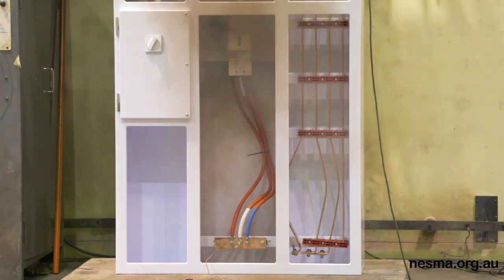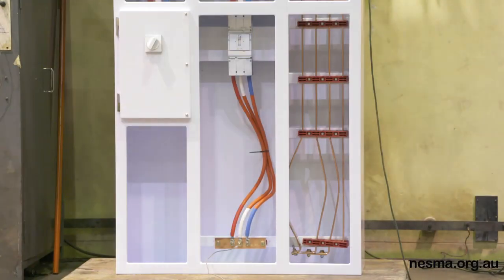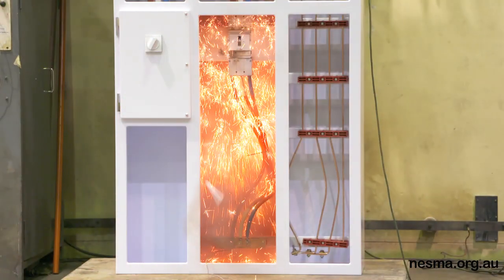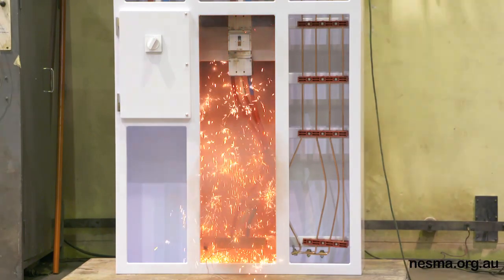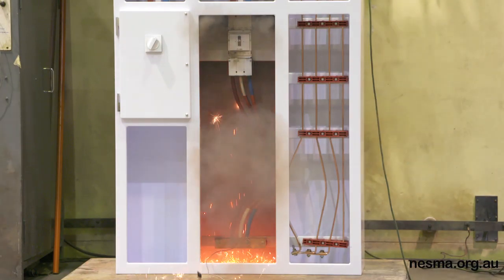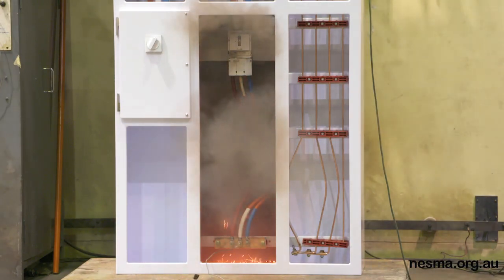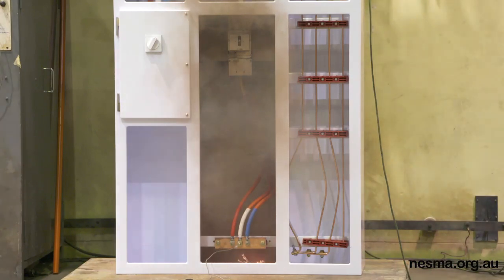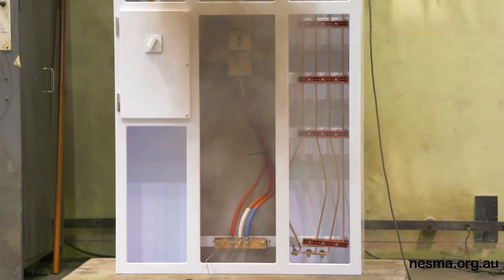One of the things to realise, because that breaker has tripped so quickly, the only support offered to those cables was a cable tie mid-span. What does happen if the circuit breakers are a larger let-through energy and you see more fault current in the load side tails, you can actually see them starting to whip around. Just as the busbars moved in that first test, the cables would behave exactly the same. And it's a matter of, if we were testing to 61439, that cable tie is deemed as primary current support. And so if we start blowing cable ties away, then that would be deemed a failure of support system.